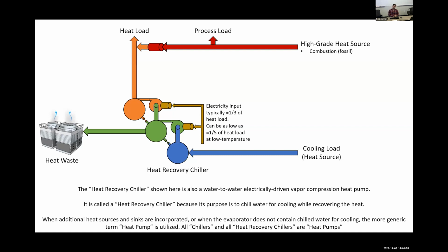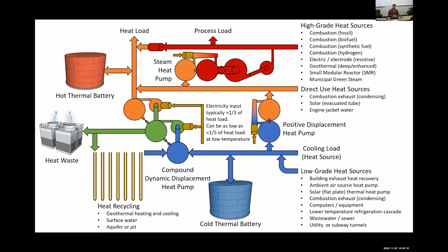And then we also start throwing the word heat pump in there, or water to water heat pump, or district heat pump. And when we do that is when we start to advance to pulling low-grade heat sources that are in excess of the actual campus cooling load. Systems start to look like this. We do have cooling load, and we can do simultaneous heating and cooling at very high efficiency because we're displacing work that would have otherwise been done just for chilling. So some of that work is saved. We do a little bit of extra work, and we can make beneficial heating off of a similar unit, going from a chiller to a heat recovery chiller.